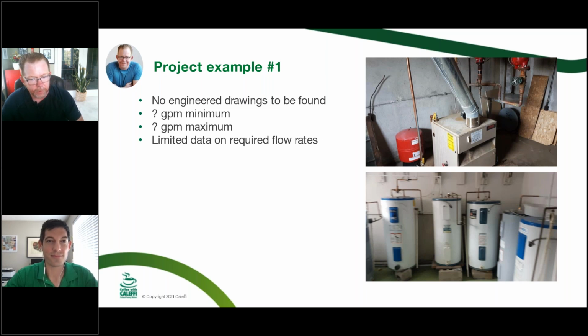One of the things we'll see a lot is that people will look at a job and go, well, I know how big the boiler needs to be. This old boiler is 500,000 BTU, so clearly that's what I need. And then you'll notice, okay, well, I think they had about 12 water heaters. We'll just base it off 12 water heaters. The reality is that's a pretty expensive solution.